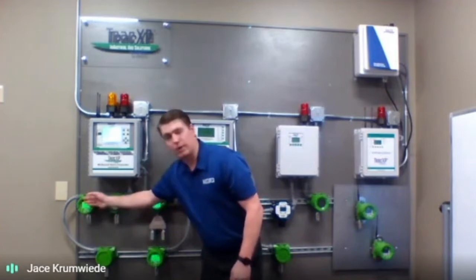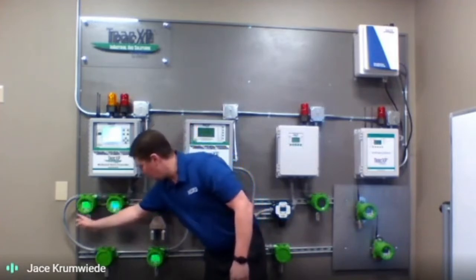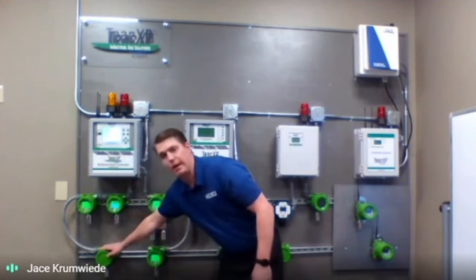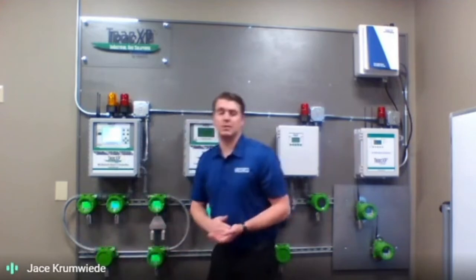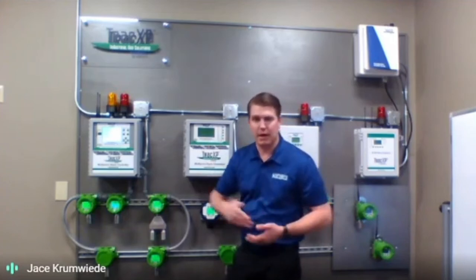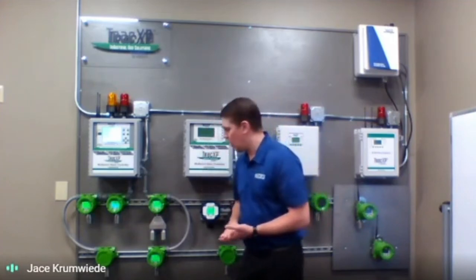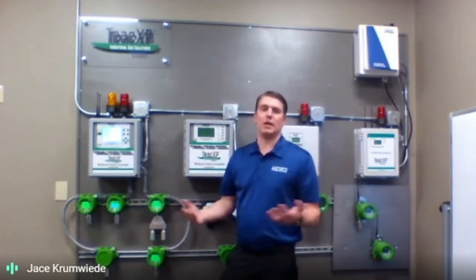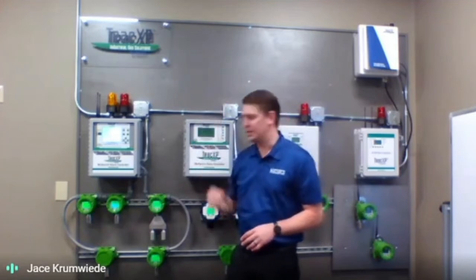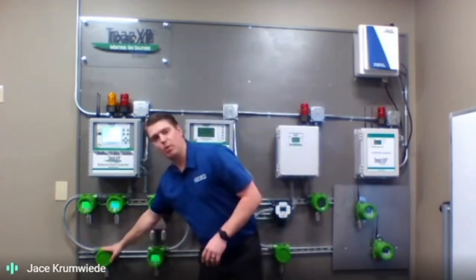see here. So it does have one integral sensor. That's where the transmitter is located, this one sensor there. And then it's actually connected right here to a remote. So sometimes you're going to want to mount a sensor up high or down low in the space, and then the other one with the display, you're going to want at breathing level or eye level. So say, for example, it's methane, and methane being lighter than air, you want it mounted high up in the space.